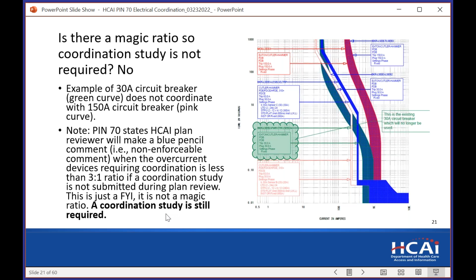So OSHPD will do an FYI comment if we see your ratio is less than 3 to 1. So you have a 20 amp branch circuit and a 60 amp main breaker. We're going to make a comment just as an FYI. It's a courtesy to you that you might be overlooking coordination. But coordination study is still required, and the system is required to coordinate at any ratio.